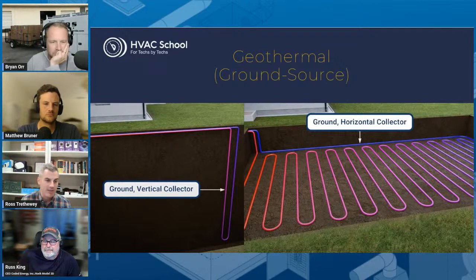But hey, if you're tapping into 50-degree temperatures where we live, that's a lot better than 0 degrees or 5 degrees. If I can use that 50-degree heat source that's in the ground inherently, and I'm trying to keep my building at 70 degrees, my delta T is only 20 degrees. I only have to boost it from 50 to 70. The heat pump can do that really easily. But as opposed to air source, I've got to bring it from 5 degrees up to 70, right? So the delta T is much wider in that arrangement.